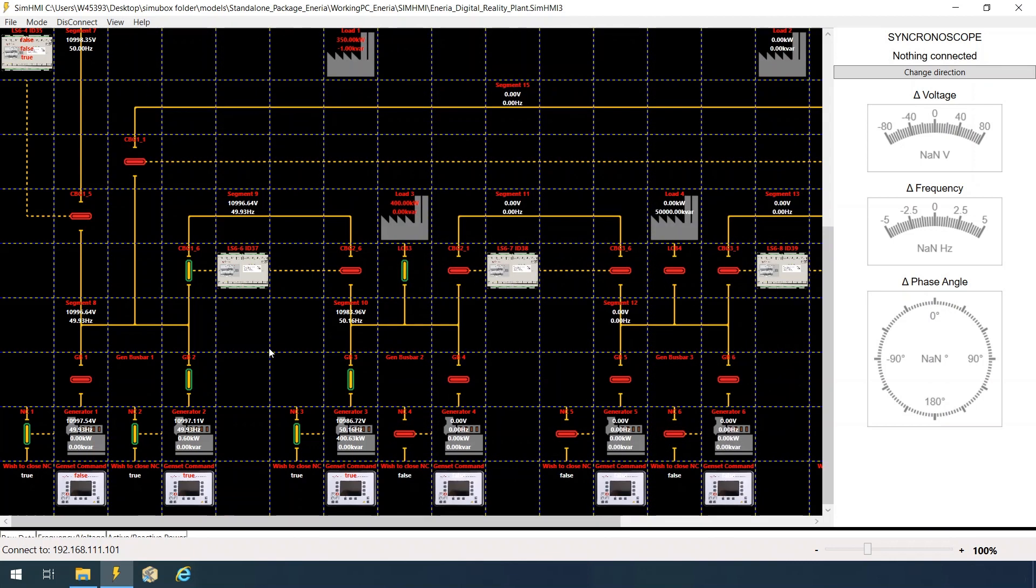This means we have our application monitored and safe from ground faults all the time. Also worth noting is that, if a generator is in cooldown and its breaker is open to be safe, it keeps its neutral contactor closed.